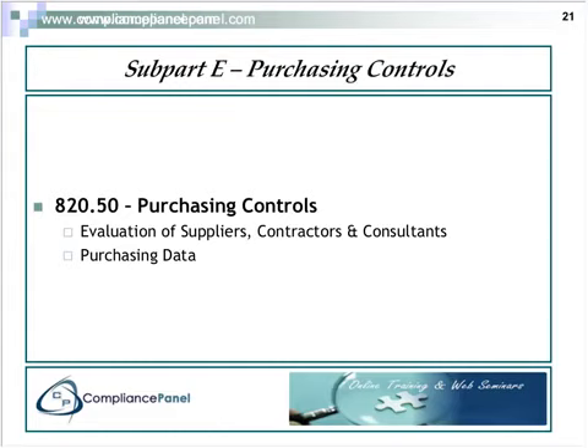Purchasing controls. It's important for all of you to understand that any materials or services that are used in the manufacture or processing of the device must be purchased from well-controlled suppliers. And this has become a big point in the FDA's audit activity, because so much material is being outsourced outside of the country. So they're concentrating a lot more on your supplier controls, how you control your suppliers.